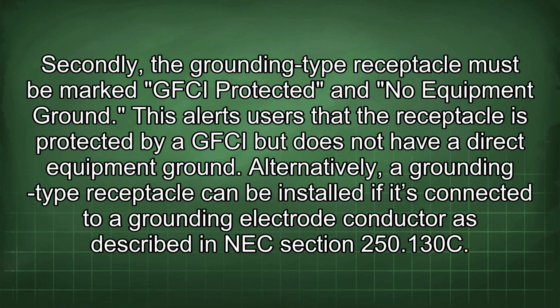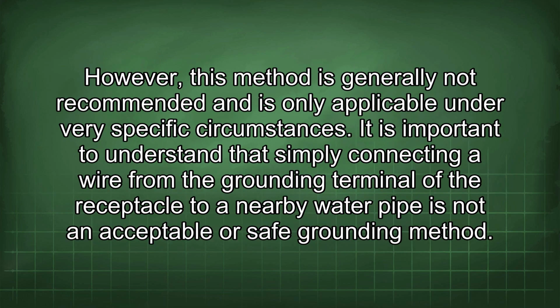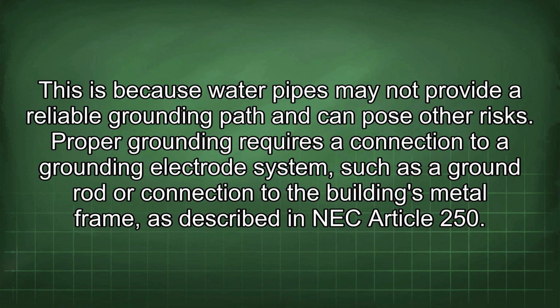Alternatively, a grounding type receptacle can be installed if it's connected to a grounding electrode conductor as described in NEC Section 250.130(C). However, this method is generally not recommended and is only applicable under very specific circumstances. It is important to understand that simply connecting a wire from the grounding terminal of the receptacle to a nearby water pipe is not an acceptable or safe grounding method. This is because water pipes may not provide a reliable grounding path and can pose other risks. Proper grounding requires a connection to a grounding electrode system, such as a ground rod or connection to the building's metal frame, as described in NEC Article 250.